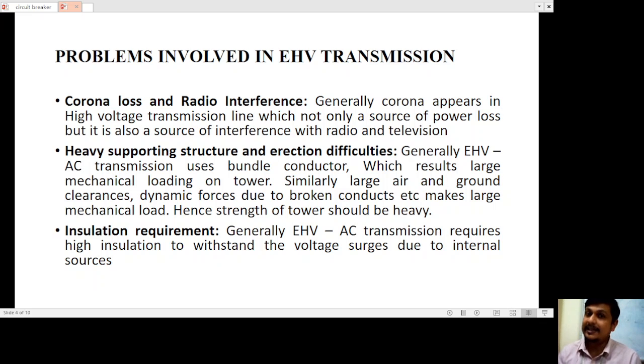As I told in earlier classes, clearance is decided based on voltage level, not current level. So if voltage is higher, clearance is higher, and the height of tower is larger, so tower strength should be high. Insulation requirement also depends on your voltage level.